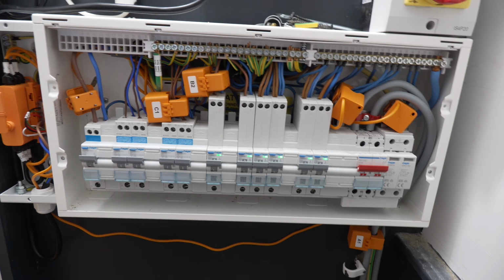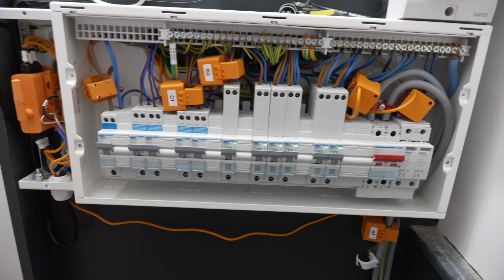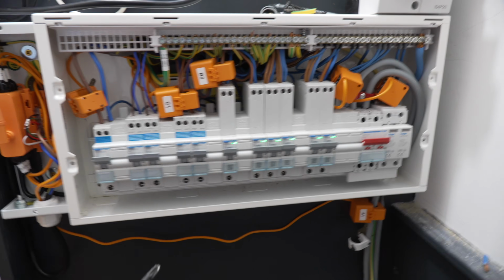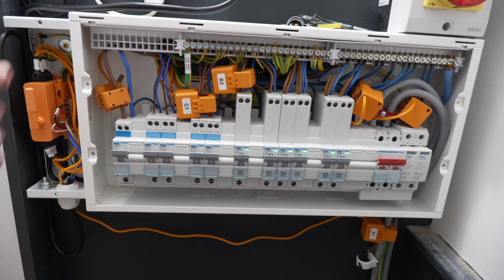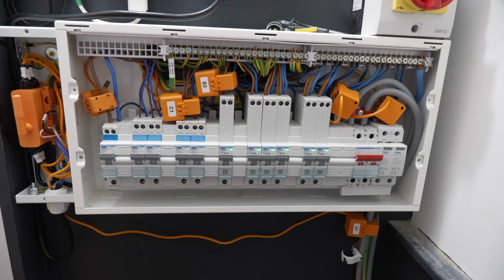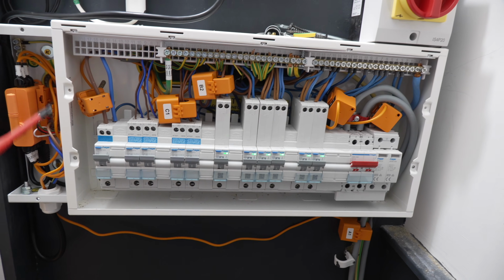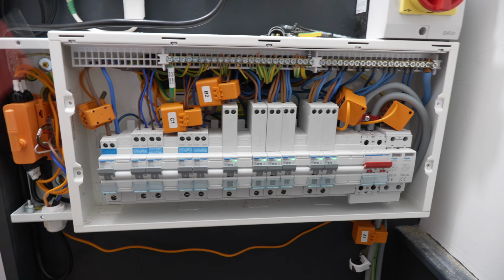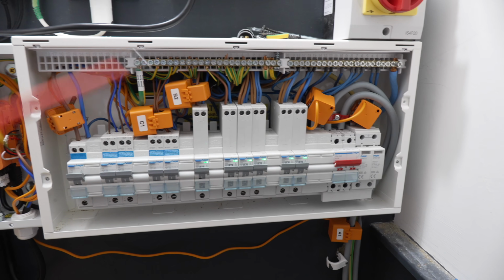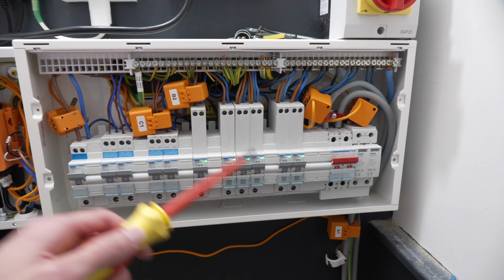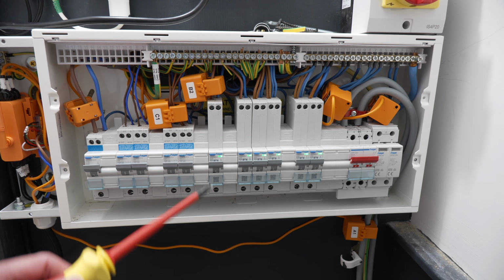Definitely have to say though, these CTs are very big. Compared to other systems where you can buy smaller CTs, you might have, say, a 100 amp CT for your grid connection, and then maybe some 50 amp CTs and 20 amp CTs for your general circuits. Using these 120 amp CTs for everything does mean that they're very big, and trying to get them in here is really awkward. In fact, if these breakers hadn't been spaced out like this, I would have really struggled to get these all in.